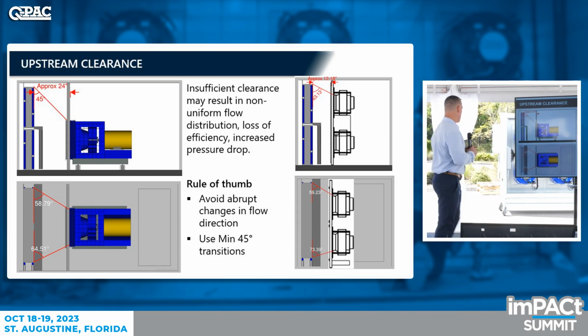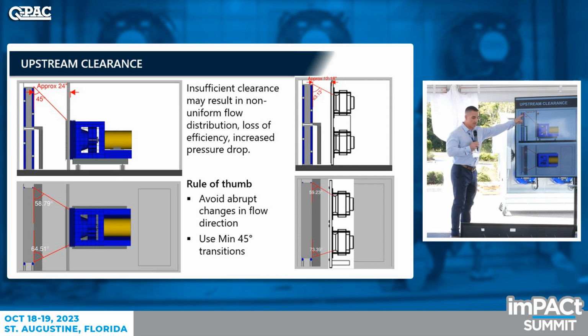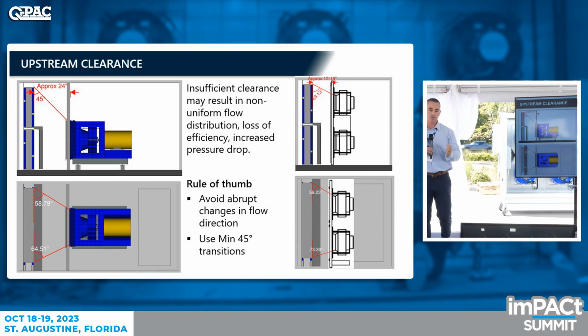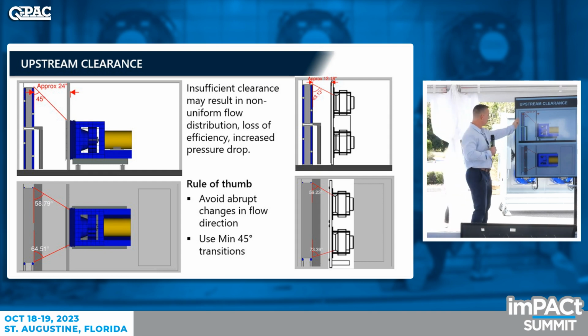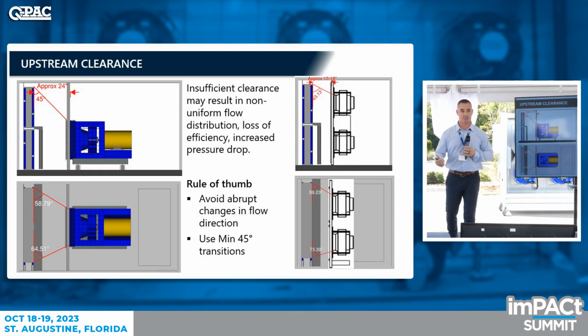You can see from the top, here's our 45-degree angle, and then here's a plan view with angles from the side of the coil. So you really do not want to get any closer than a 45-degree angle from the top and the sides of a unit to the inlet of your fans, okay?